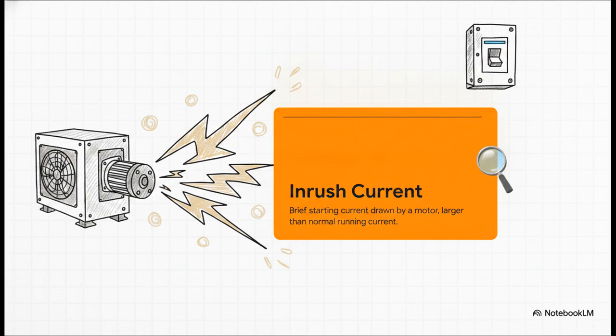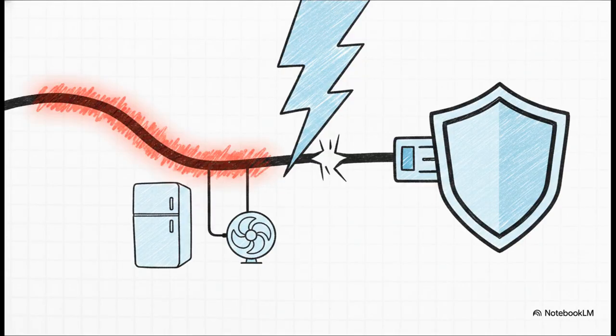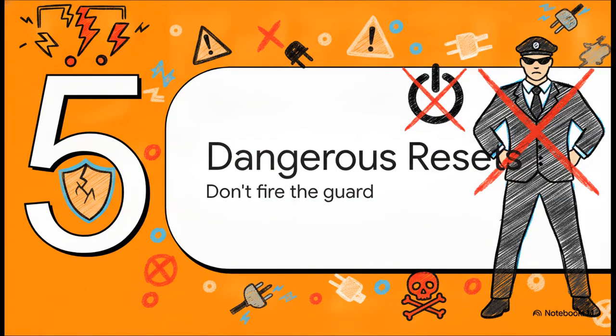A properly designed circuit handles this initial jolt completely fine under normal conditions. But when you combine that massive gulp of electricity with a circuit that is already heavily loaded and hot, it becomes a perfect storm. Throw in low voltage, repeated compressor starts, or aging equipment, and that initial surge easily crosses the breaker's time current limit. The bodyguard steps in and trips the system. Which takes us to a very crucial safety topic.